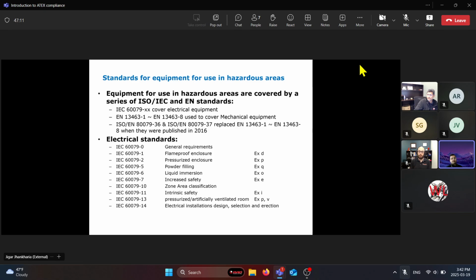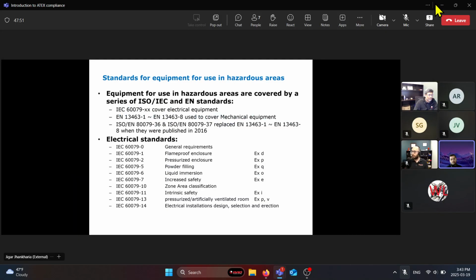So if you don't have access to that standard, I would highly recommend you download or purchase it, which is IEC 60079-0. I believe the latest edition is 2017 or 2018. That pretty much is the basis of everything you would design for zone classification. If you would like to get ATEX or IECEx certification, that is one standard I would recommend you read over. It has tables, requirements, creepage, clearances, IP rating requirements, most basic requirements for a product to be certified for IECEx and ATEX. Sorry, I know one of your questions was about IP rating. The standard you're referencing there was the -0? Yes, that's the basic standard.